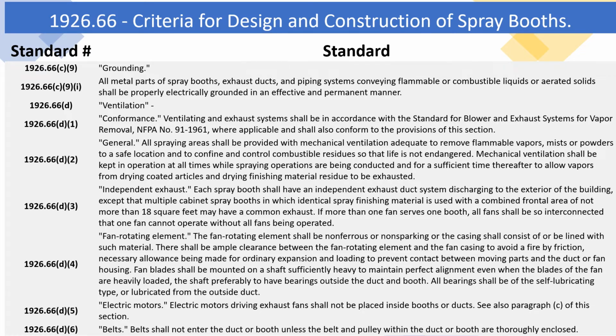1926.66(d)(4) Fan rotating element. The fan rotating element shall be non-ferrous or non-sparking, or the casing shall consist of or be lined with such material. There shall be ample clearance between the fan rotating element and the fan casing to avoid a fire by friction, necessary allowance being made for ordinary expansion and loading to prevent contact between moving parts and the duct or fan housing. Fan blades shall be mounted on a shaft sufficiently heavy to maintain perfect alignment even when the blades of the fan are heavily loaded, the shaft preferably to have bearings outside the duct and booth. All bearings shall be of the self-lubricating type, or lubricated from the outside duct.